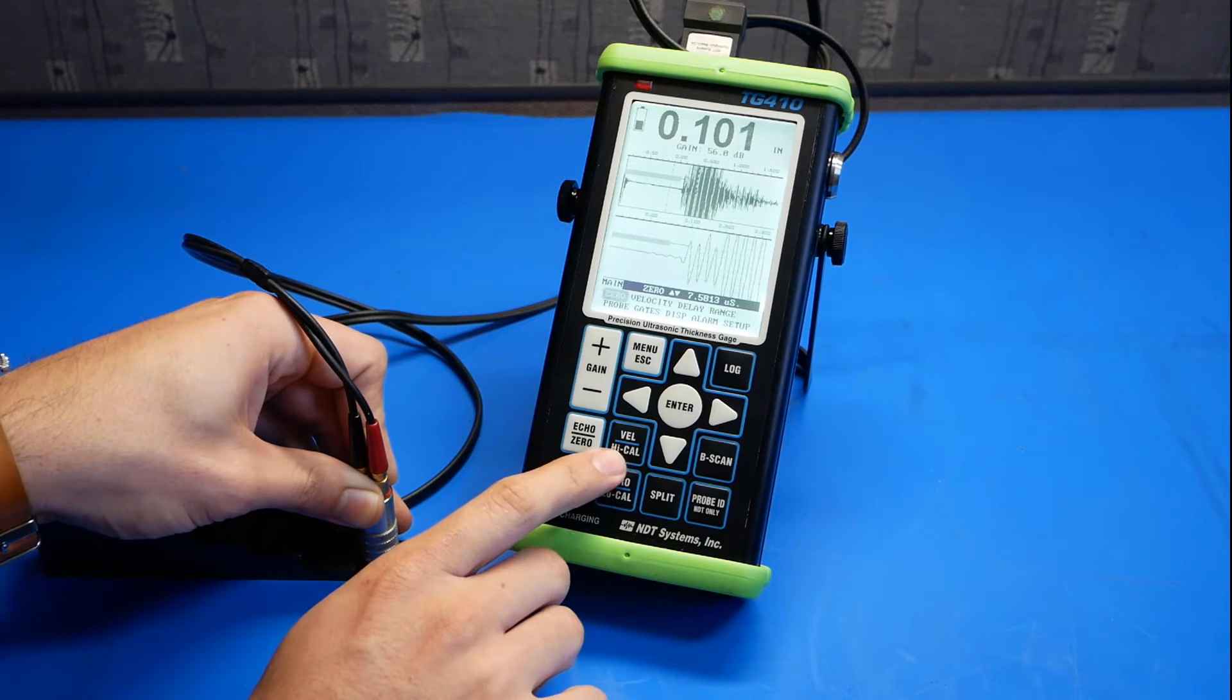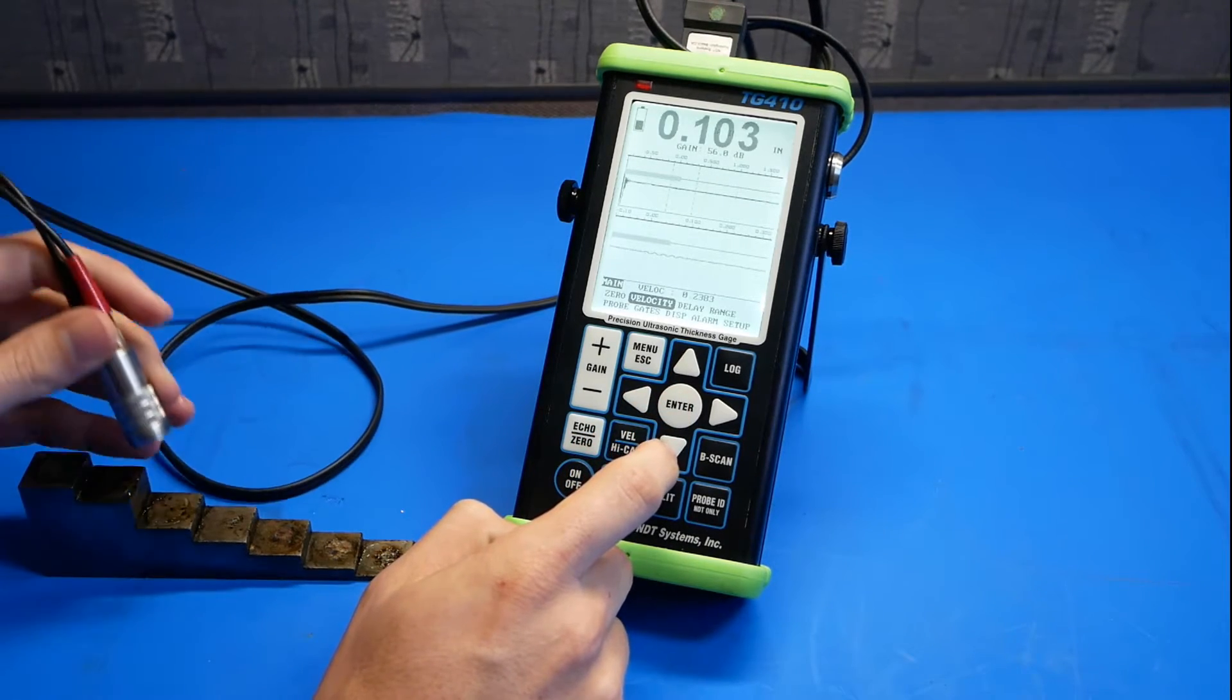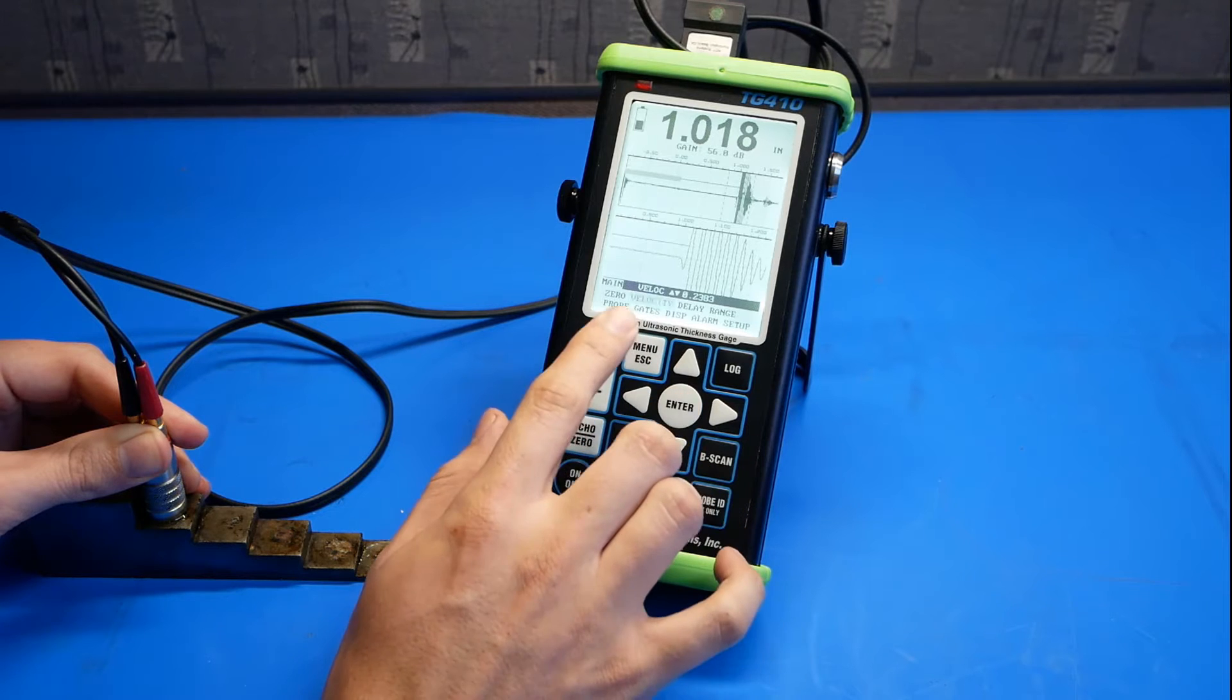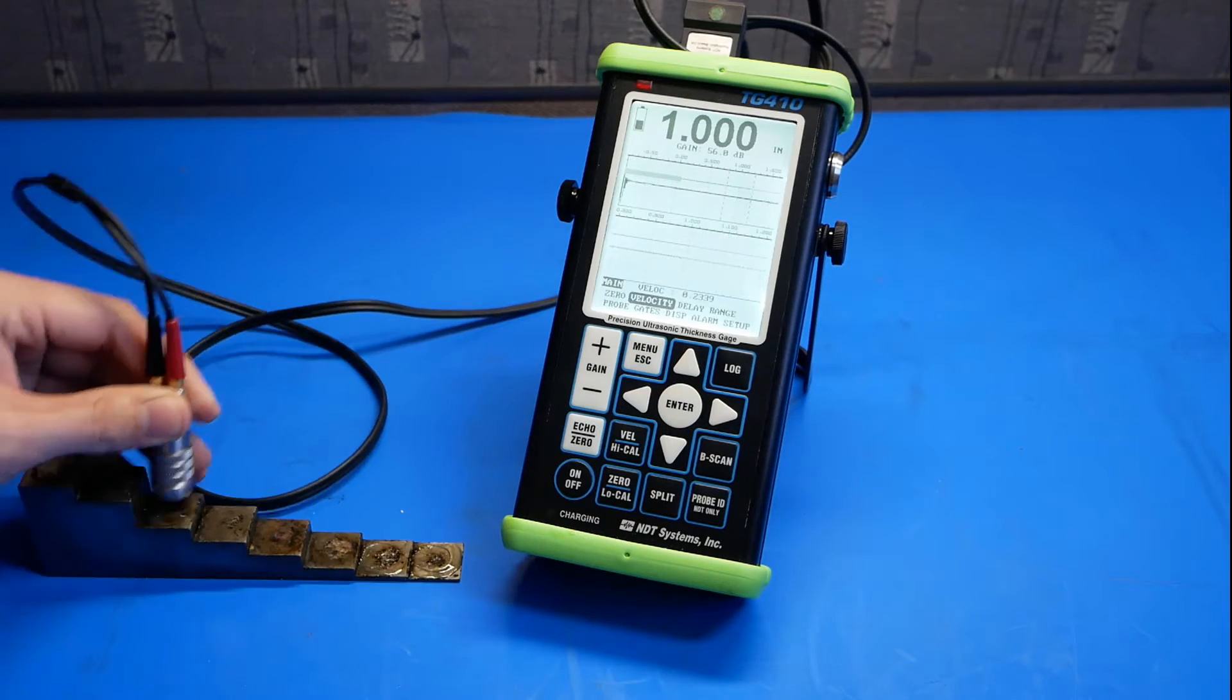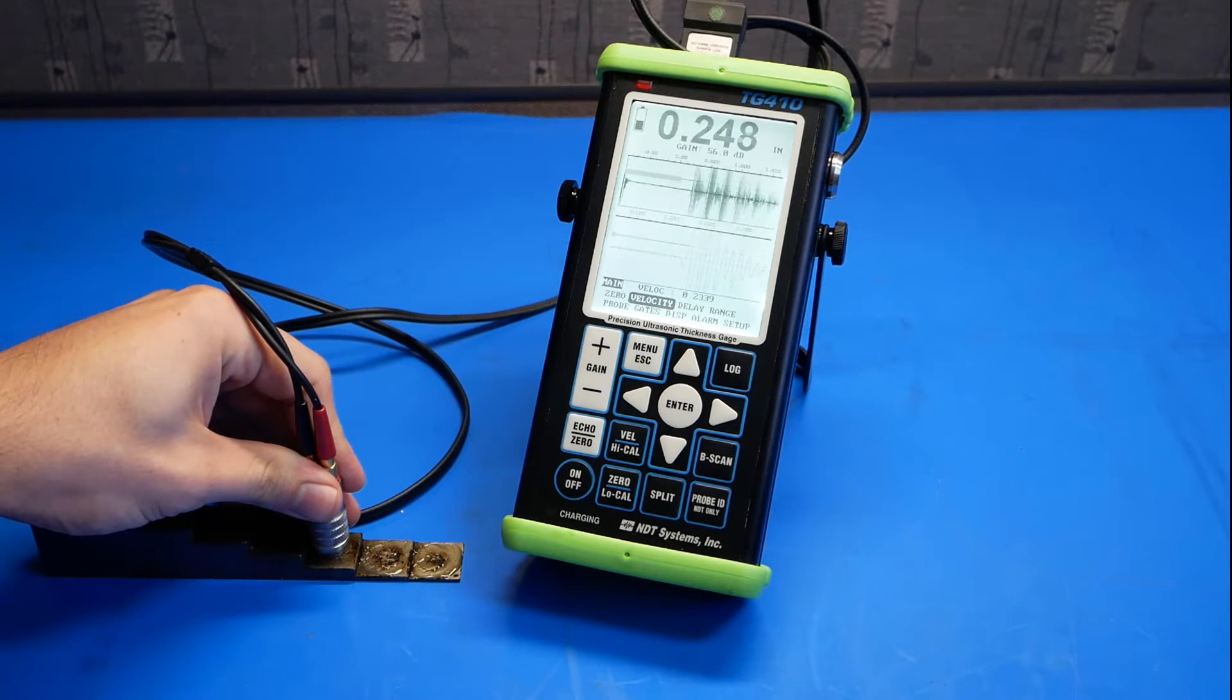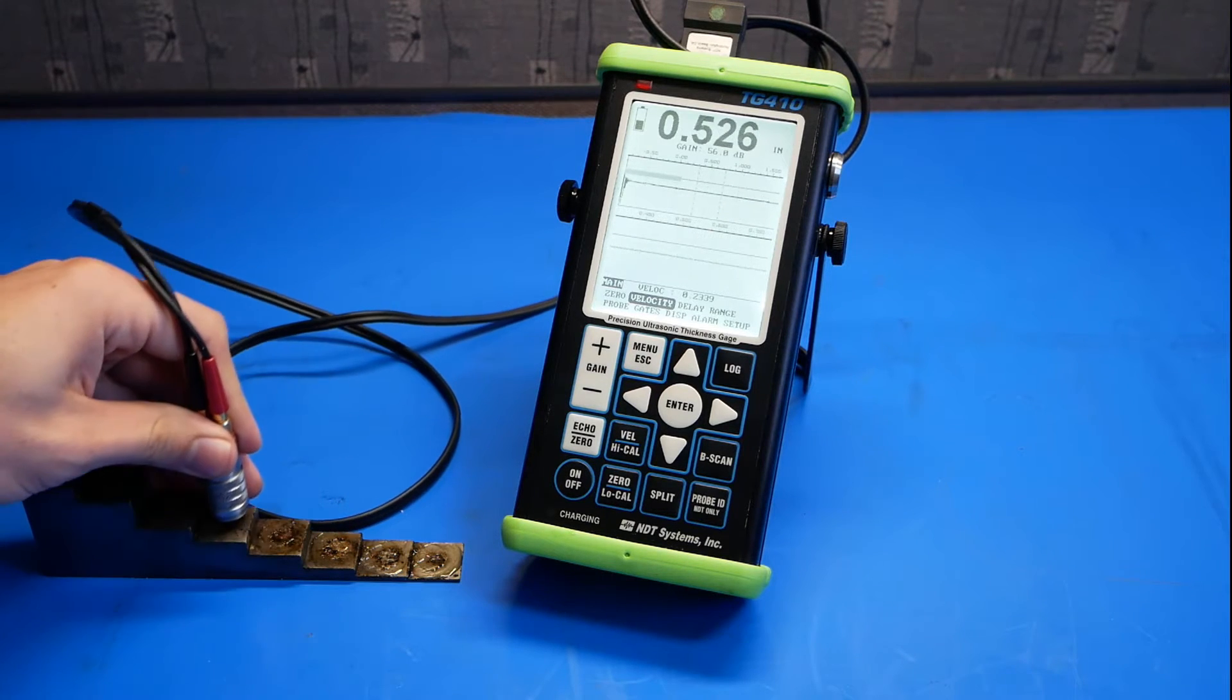Next, go to the velocity high cal button. Push enter, and go ahead and couple it to a high thickness region. In this case, 1 inch. We're going to adjust our velocity until our gauge reads 1 inch. Going back to the low thickness, we can see that the readings are within tolerance as we increment thickness along the step wedge.